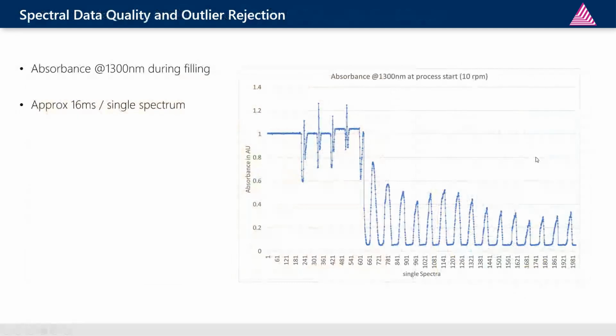Now let's look at something we are using for outlier rejection. The blue curve on the right is only the absorbance value of the spectra at the wavelength 1300 nanometer. 1300 nanometer is a wavelength where nothing else is going on, so it is a good baseline. And you can see before the filling process is started, we have a stable baseline with a high value. It's just a background signal within the feed frame simulator. Then we start to fill it, and we can see the absorbance values going up and down.